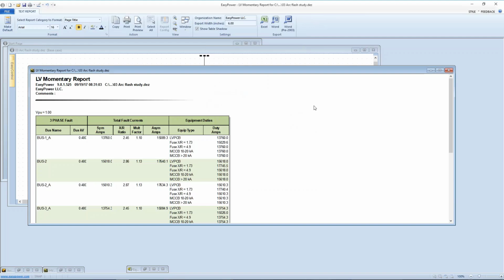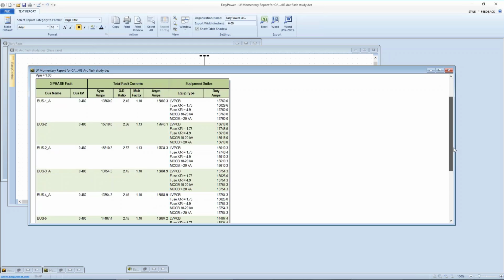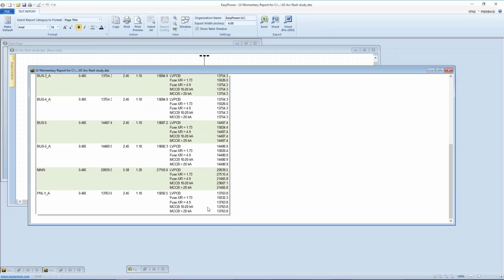Other reports are going to be my low voltage half cycle report. And again, it's showing me each bus, the worst case current, the X over R ratio that the tool has calculated for that part of my system, and how it's compensating on each particular device according to the manufacturer's test environment. And the tool automatically accommodates what that compensation needs to be. And so this indicates that I don't have any other errors as far as equipment duty.